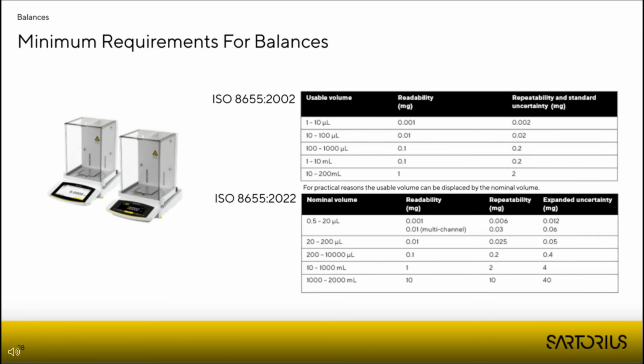If you look at the second table, with the new ISO, a 6-place balance is now needed for pipettes up to a nominal volume of 20 microliter, which means that the new ISO requires between 11 and 20 microliter a better balance than the old ISO. And this is the same, for example, for a nominal volume of 200 microliter. Up to now, a precision balance with 4 places was okay. With the new ISO, now an analytical balance with 5 places is needed here.